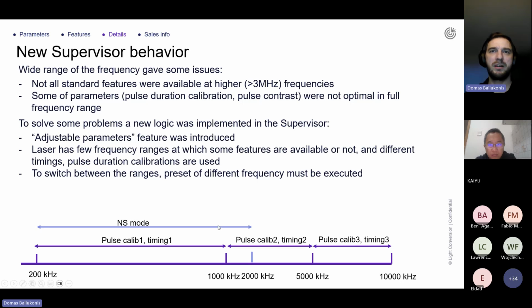Here you can see an example of 3 ranges: between 200 kilohertz and 1 megahertz, one from 1 to 5 megahertz, and one from 5 to 10 megahertz. Let's say you are working at 500 kilohertz, so certain pulse calibration and timing parameters are applied. If you want to change the frequency to 3 megahertz, you need to apply the preset. In that way, the laser will apply different timings and pulse calibration tables that are more optimal for that frequency range. So basically, that is the main difference in the laser firmware side and usage of the laser.